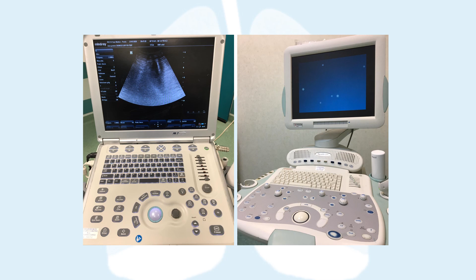The convex probe has a low frequency of the ultrasound beam emission, going normally from 2 to 5 MHz. This is considered a low frequency probe, meaning that it is able to penetrate the tissue at a greater depth. This is therefore the correct probe for the study of deeper organs and in general parenchymal tissues. When performing a pulmonary ultrasound, this probe will therefore allow us to evaluate the pulmonary parenchyma, but will also be less precise for the evaluation of more superficial structures like the pleura.